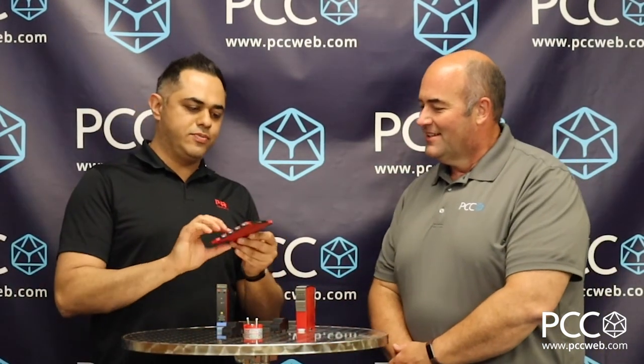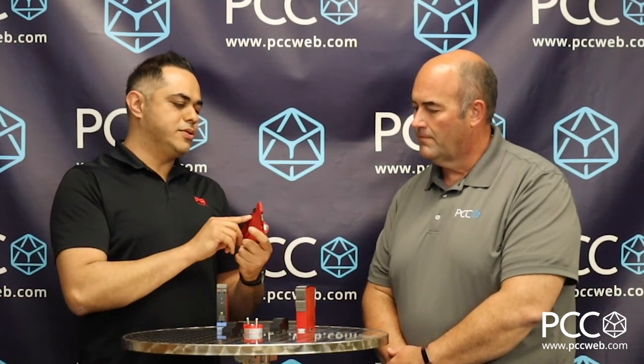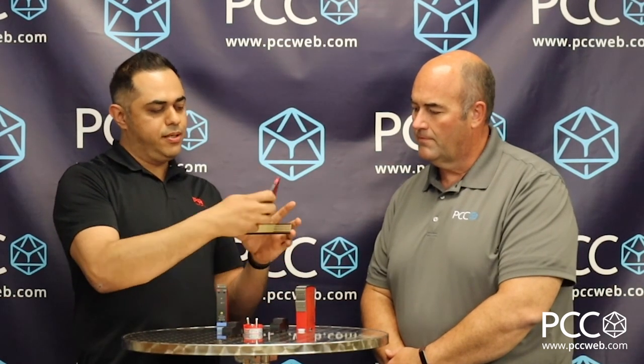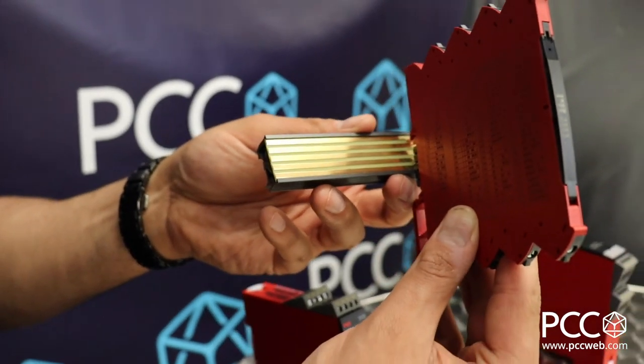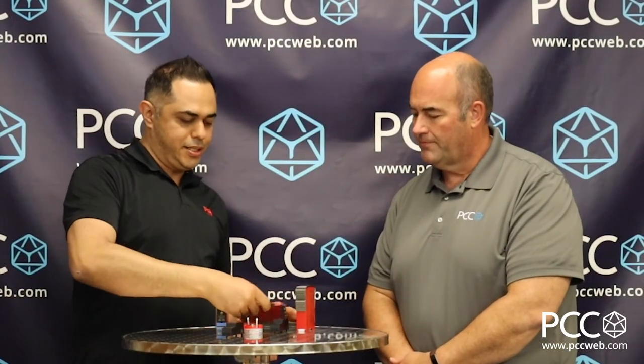We've got a patent on this unit here as well. It's an isolator known for its space-saving design — it's only six millimeters wide, and you can stack these units next to each other with no air gap required. There are two versions: a loop-powered version where you just loop them in, and a powered version that has a power module at the back where you clip it onto our power rail. You can stack as many as you want, and if you feed one of them with power, the rest get powered through the backplane — saving on wiring costs.